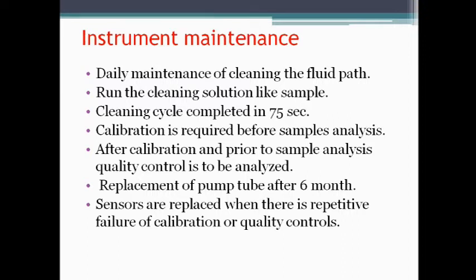It is completed in a maximum of 75 seconds. After cleaning, calibration is required. After the calibration, the control sample is run, and after that the sample is run. Sensors are replaced when there is repetitive failure of the calibration or quality controls.